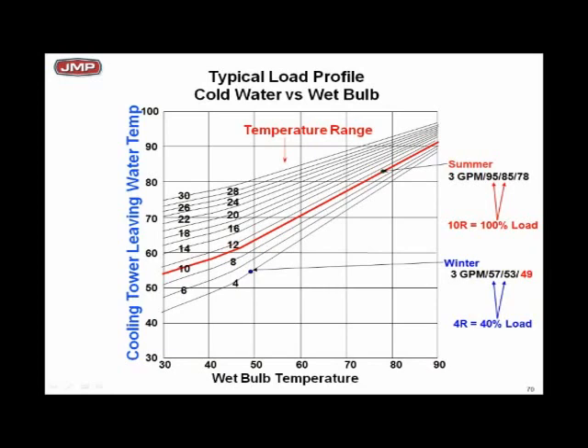So let's take a point, and I hope you can learn this one thing about towers. So please pay attention. A lot of people never quite grasp what I'm trying to get across to you now. What happens to the approach? What happens to the cold water temperature I can make in a tower as the wet bulb goes down? What happens? We're talking about cooling a building at 45-degree wet bulb and 50-degree dry bulb. What happens to that approach on a nominal tower that we pick for the summertime when we look at the wintertime conditions? What is that approach?